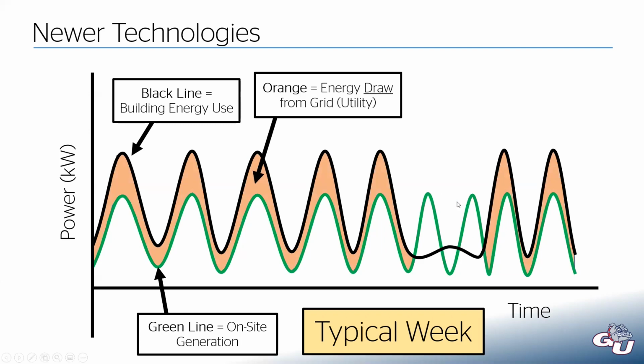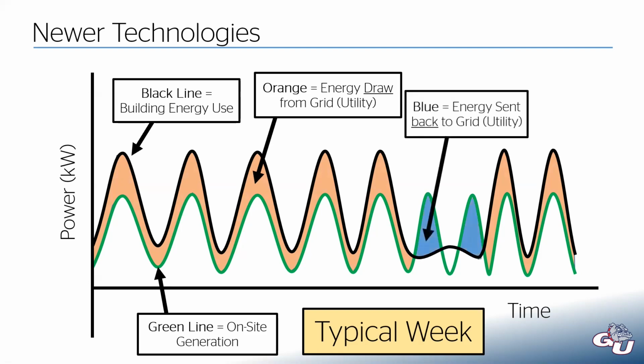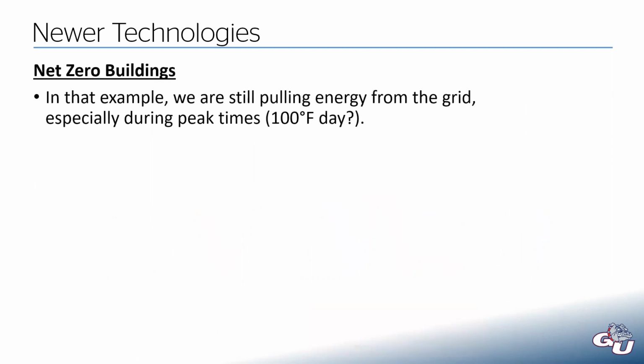But then you notice, here on the weekend, our PV systems didn't reduce their output. They don't care if the building's occupied. They just care about whether the sun's out. And so now we have an inverted area here in blue, which is going to be the energy that we're sending back into the grid. So some times of the day or week, we're pulling energy, we're buying energy from the utility, and then we have these other times where we are actually selling them energy. So in that example, we're still pulling energy from the grid.